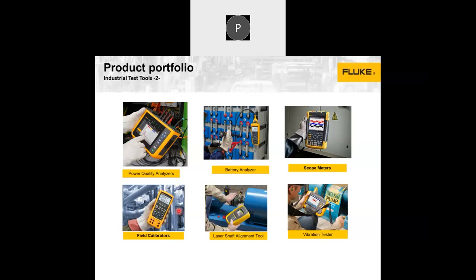We also have field calibrators, which can help you identify things especially when you have mechanical signaling systems, where you may use 0 to 20 milliamps or 0 to 50 volt kind of signals, or 24 volt kind of signals to control certain things, or sensors like temperature or pressure sensors to give alarms or control signals.